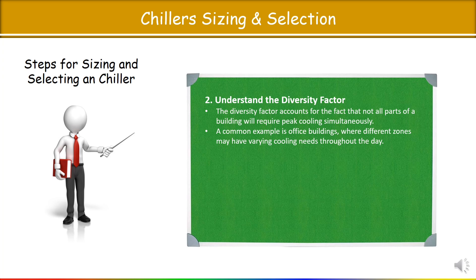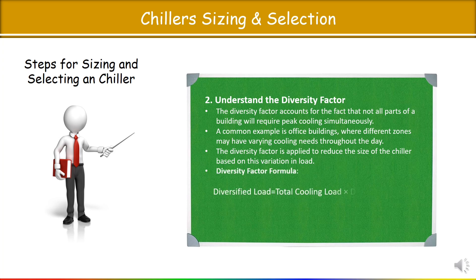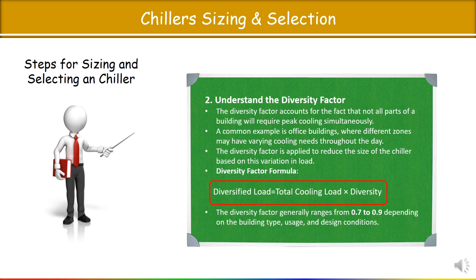A common example is an office building where different zones may have varying cooling needs throughout the day. The diversity factor is applied to reduce the size of the chiller based on this variation in load. The formula is: Diversified Load = Total Cooling Load × Diversity Factor. The diversity factor generally ranges from 0.7 to 0.9 depending on the building type, usage, and design conditions.